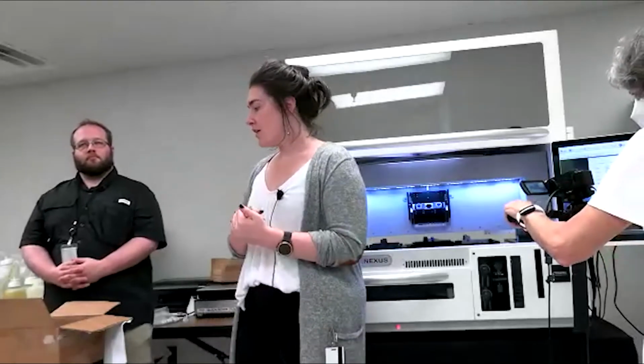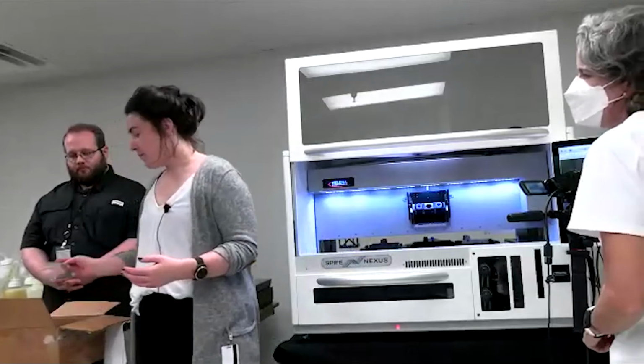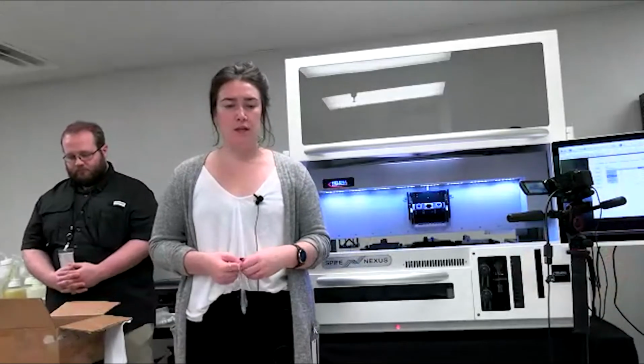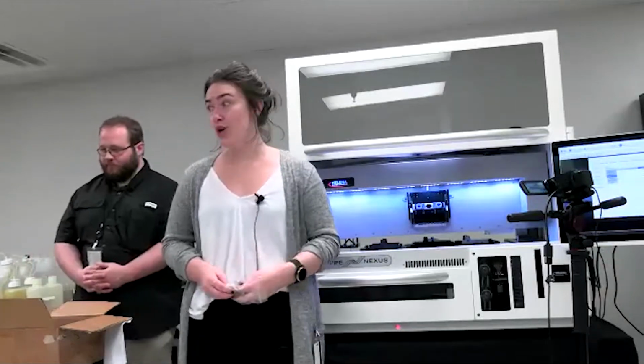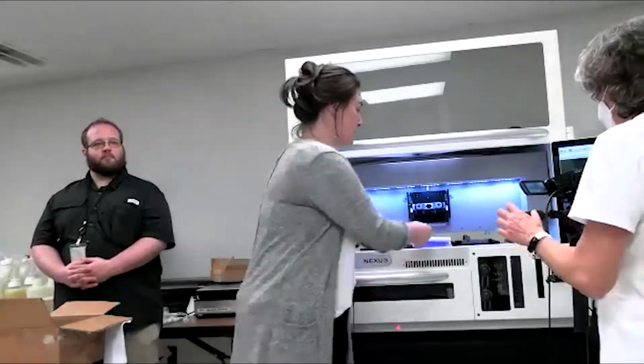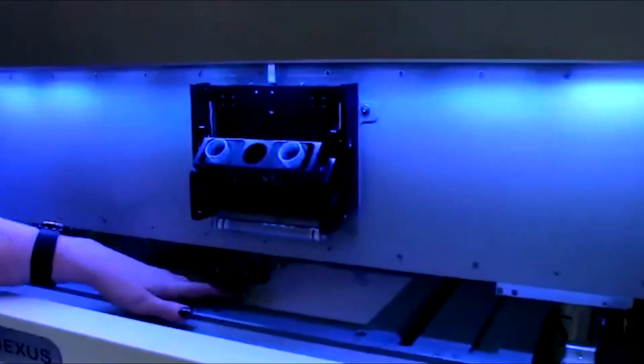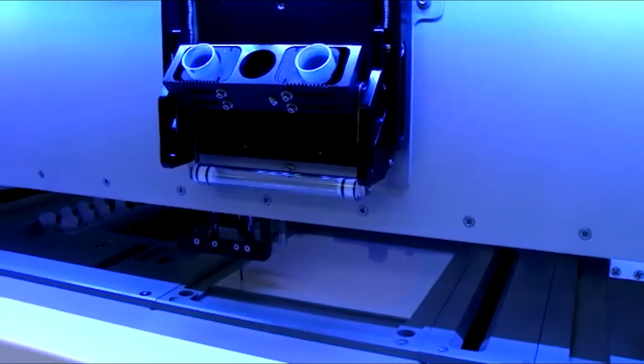Yes, absolutely. The things that are more sensitive have more of what we call no-go type calibrations. So when you're calibrating the Z on the platen, for instance, let me move this. When you're calibrating your height on this platen, you'll use two feeler gauges. One should slide under easily, one shouldn't.